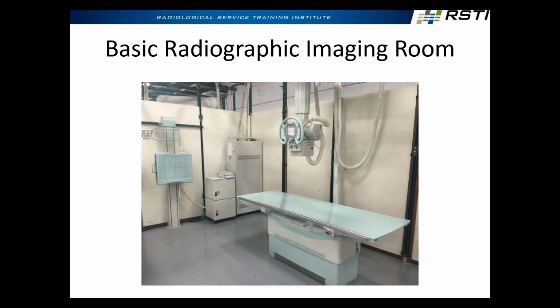But inside that tube, we've got some stuff going on. We have our X-ray tube insert. Now, when it comes to replacing an X-ray tube, we don't replace just the insert. We replace the whole assembly, right? Because there's a lot of stuff going on there. There's oil, there's all kinds of things. But this is where we're going to make that X-ray beam. And when we make a beam, we're producing not just one wavelength, we're producing a bunch of them. We're producing what I would describe as a polyenergetic beam, a beam consisting of many wavelengths and frequencies, right?